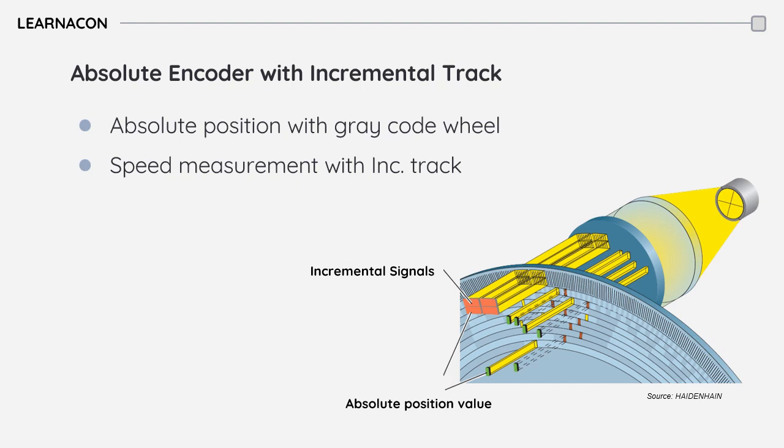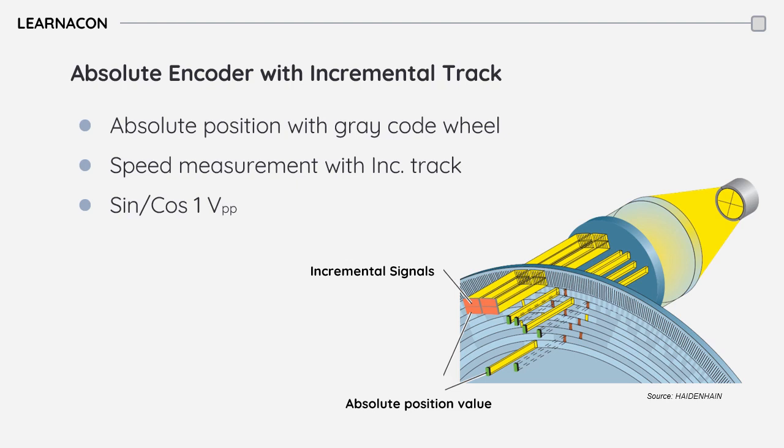The incremental track that is offered in sine-cosine version can be used for precise speed measurement, while the absolute track provides an accurate absolute position reference for initialization and fault tolerance. By combining these two functions in one device, an absolute encoder with an incremental track provides a cost-effective solution for high dynamic motion control applications.